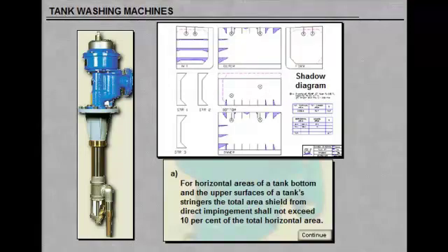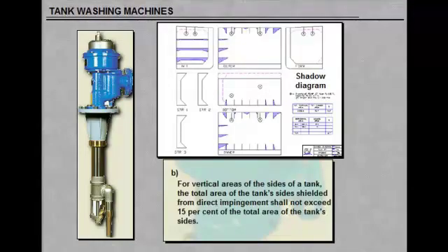For vertical areas of the sides of a tank, the total area of the tank's sides shielded from the direct impingement shall not exceed 15% of the total area of the tank's sides.